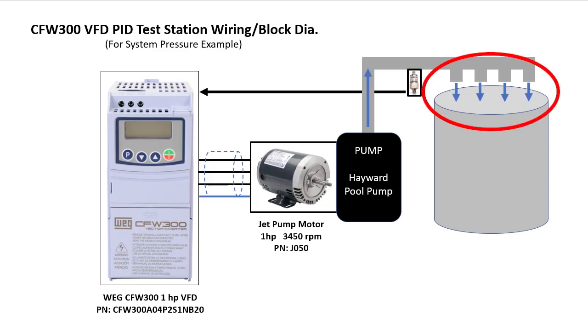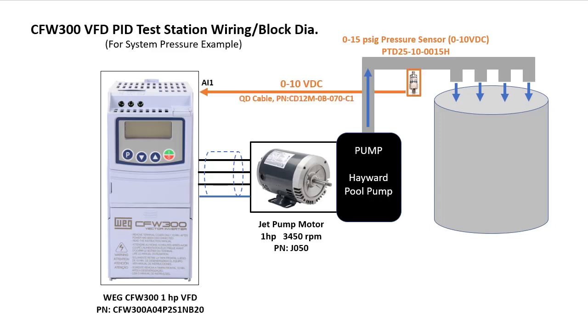This 15 psi sensor sends a 0 to 10 volt signal back to the drive so it can monitor the system pressure. That requires an external 24 volt DC supply.